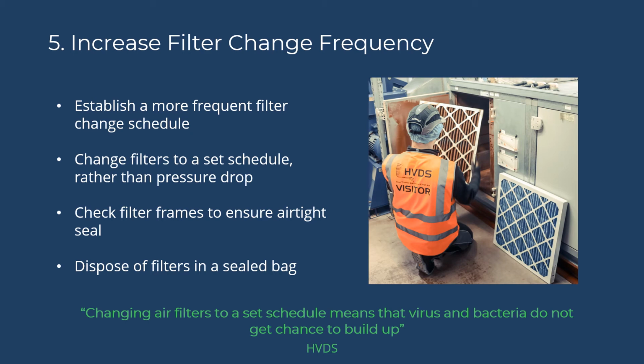Filter frames should also be checked for an airtight seal. Particles can bypass the seal if it has been fitted incorrectly or if the silicone around the filter frame has perished over time. CIBSE advises that air filters should be changed with systems turned off where possible and that old, dirty filters should be disposed of responsibly.